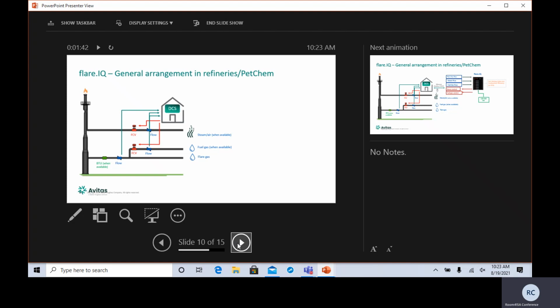What the assist does in a flare is it really promotes mixing of your system. So that provides smokeless operation and better total combustion by your flare tip. And so you have a hopefully Panametrics ultrasonic steam meter in place here for good turndown ratio, and also a valve. Now when it comes to these two additional lines, if you want to increase your BTU content, you add gas. If you want to make sure it's smokeless operation, you add steam, but that reduces your BTU content. So managing this is a real balancing act.